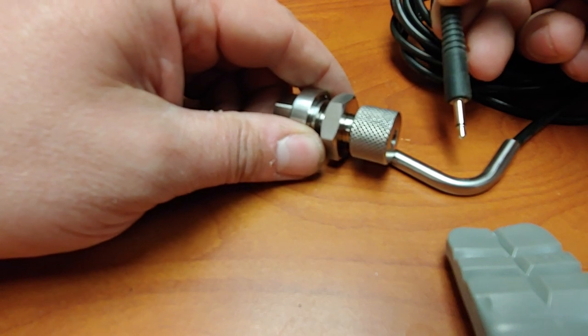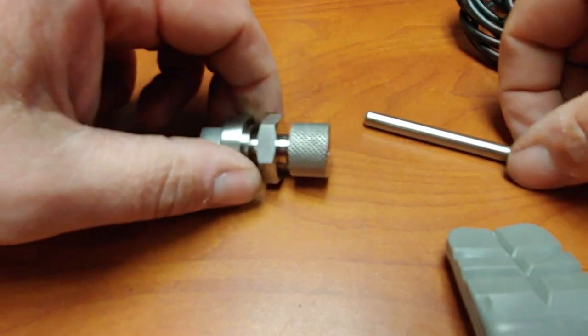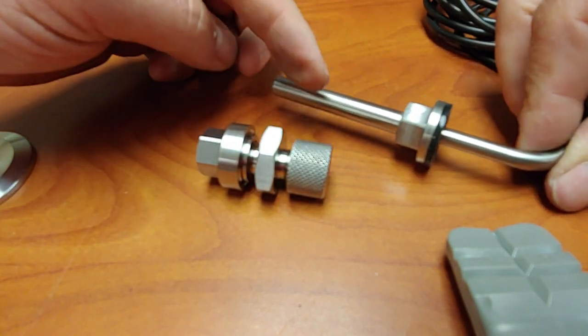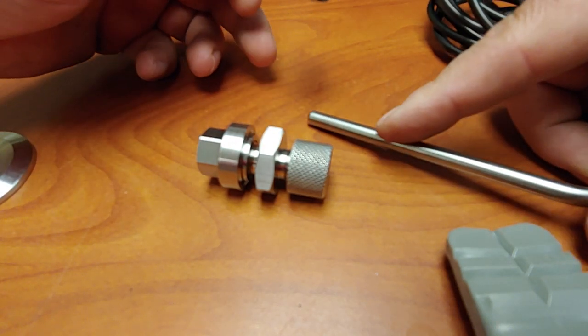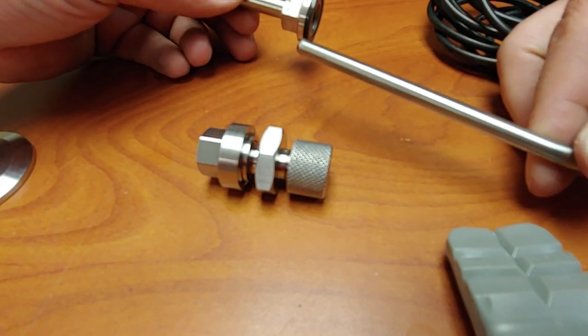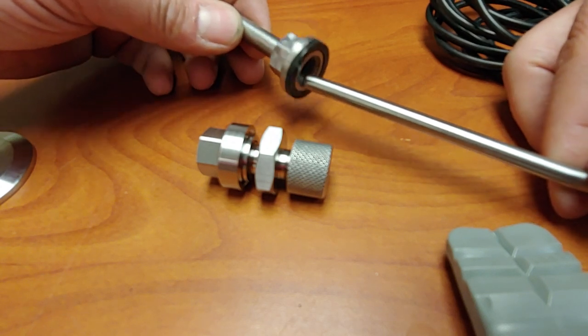Why is that? Well, I don't like the fact that the heat has to go all the way through this stainless, through a layer of air, and then into this stainless and then into the probe itself. So you're going to have a slight inaccuracy and a definite time delay between temperature changes when you use the thermal well.